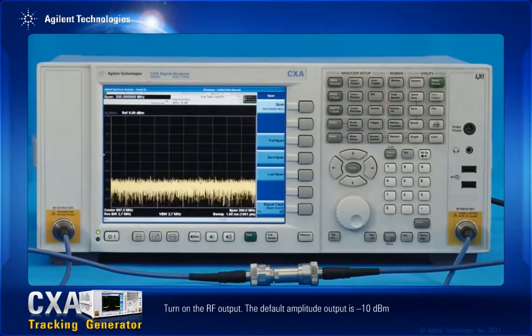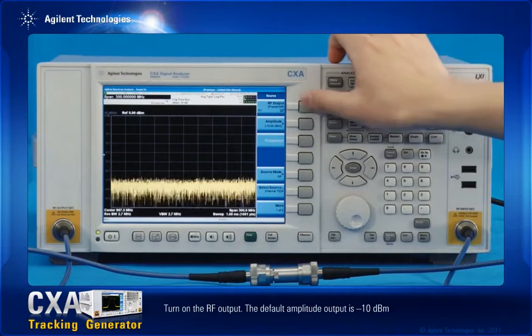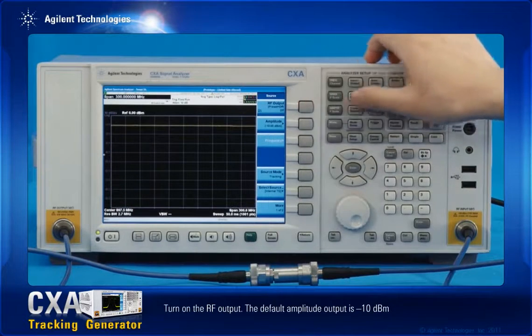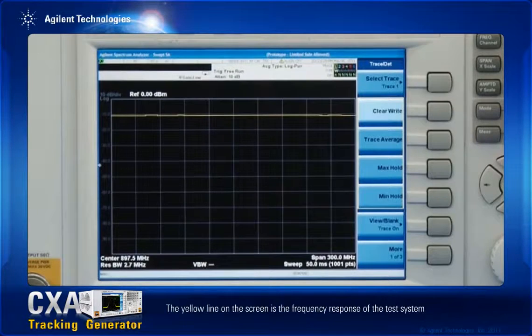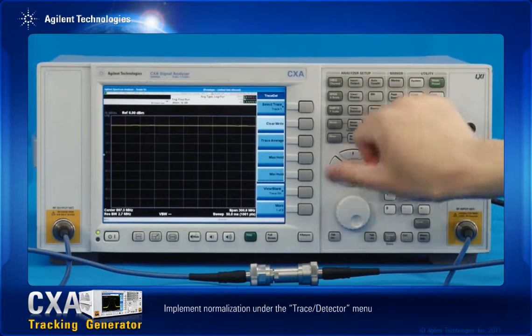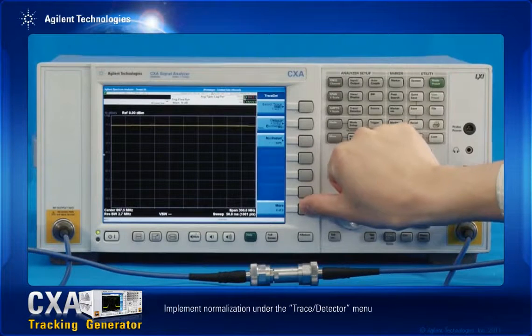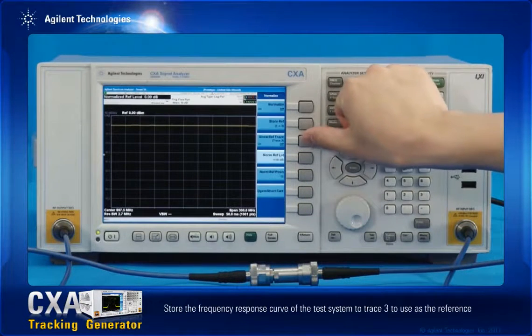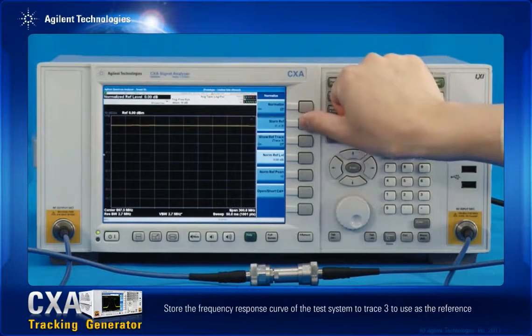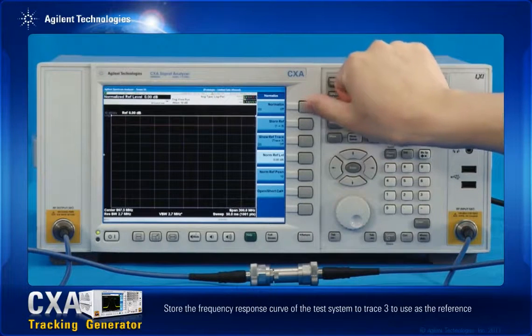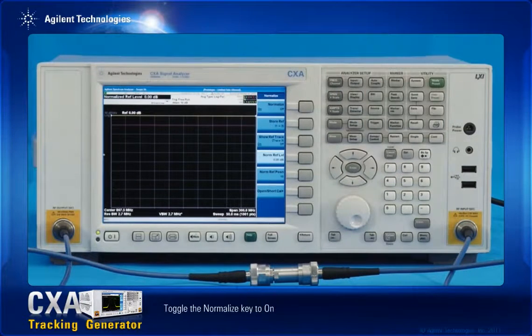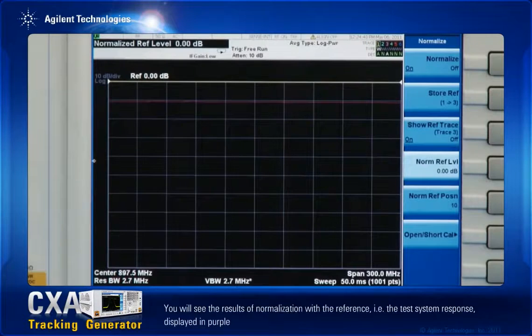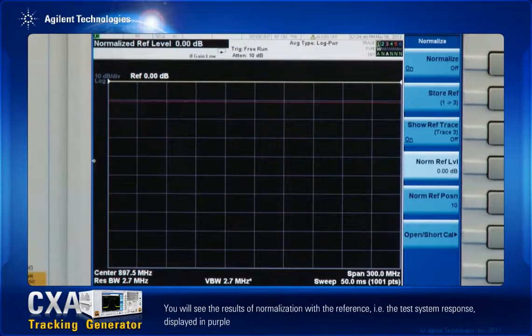Turn on the RF output. The default amplitude output is minus 10 dBm. The yellow line on the screen is the frequency response of the test system. Implement normalization under the trace detector menu, and store the frequency response curve of the test system to trace 3 to use as the reference. Toggle the normalize key to on. You will see the results of the normalization with the reference, i.e., the test system response, displayed in purple.